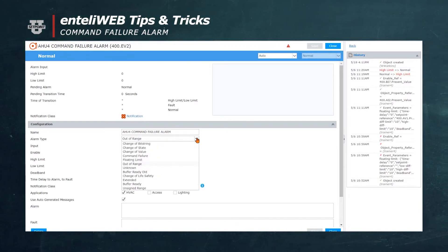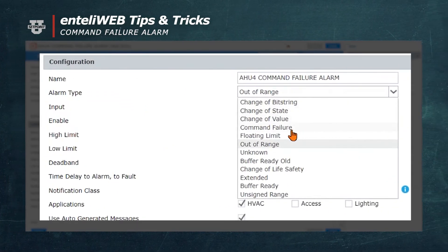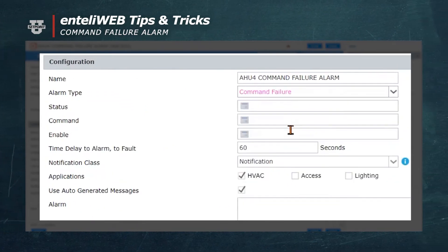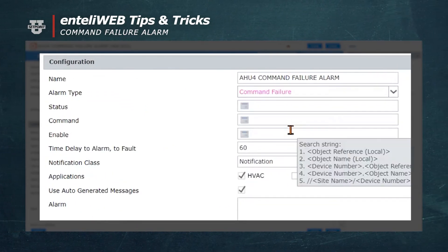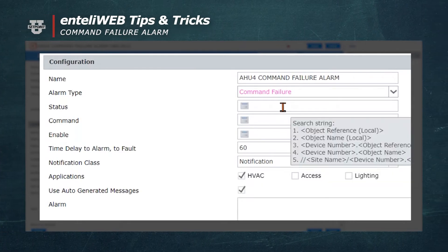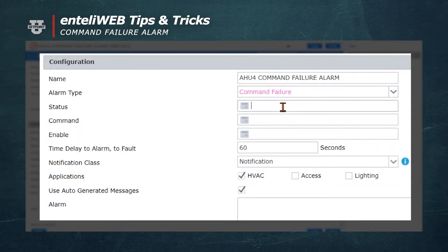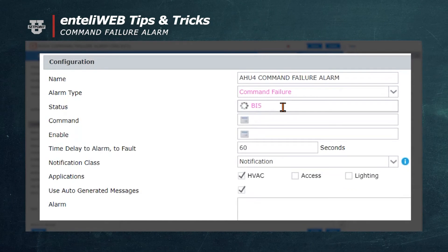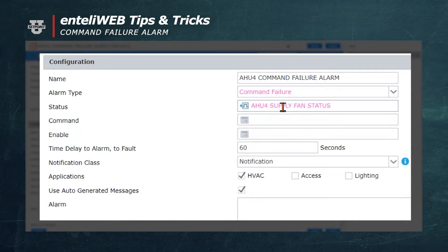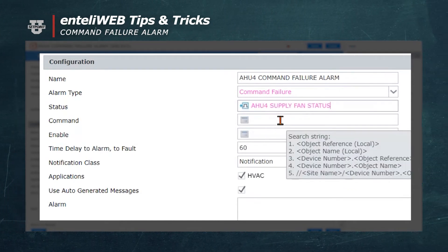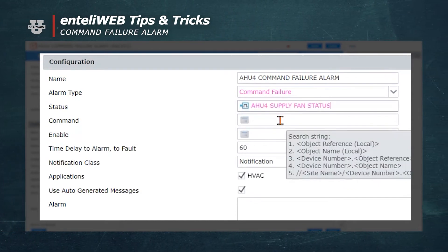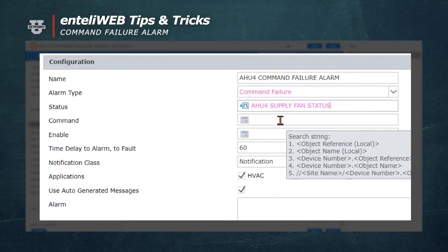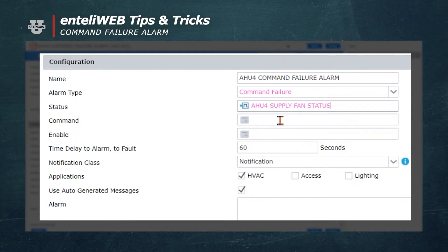From there we'll go to the alarm type drop-down menu and select Command Failure. Notice that it asks for the status, which in this instance is BI5. Note that the name is converted to AHU4 Supply Fan Status, so you know which air handling unit it belongs to. This tells us if the unit is running or not.